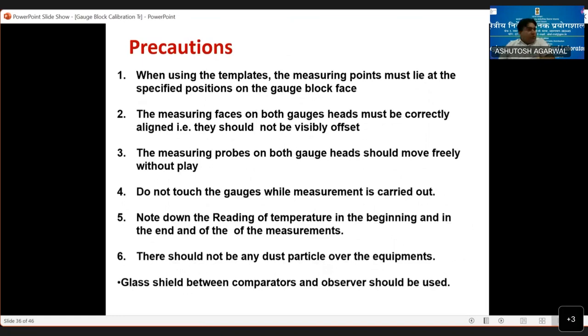Precautions: what are the precautions we should take when using the template? The measuring point must lie at the specific position of the gauge block face. So gauge A and gauge B should be at the same position. Both center length deviations should be at the same point, the center position. It's not like one is loose and one is tight. You make a template like this. The measuring face on both gauges must be correctly aligned, the same thing which I am telling. They should not be visibly offset. The measuring probe on both gauge heads should move freely without play.